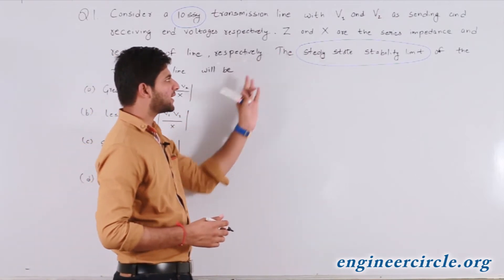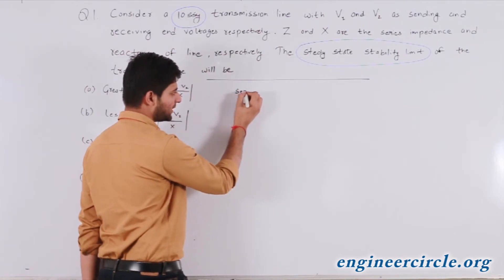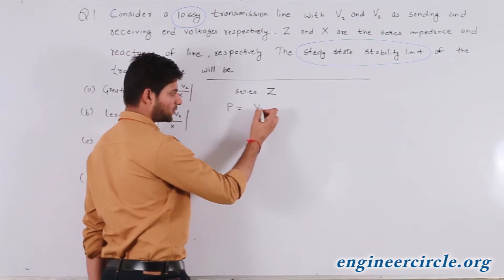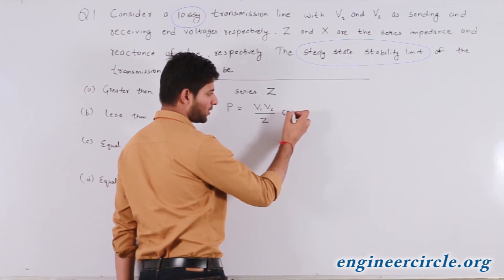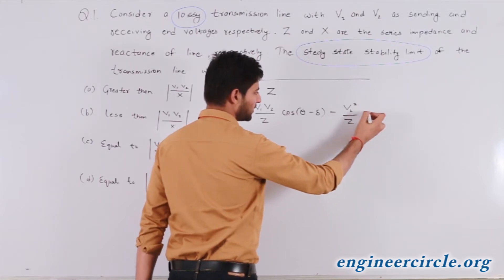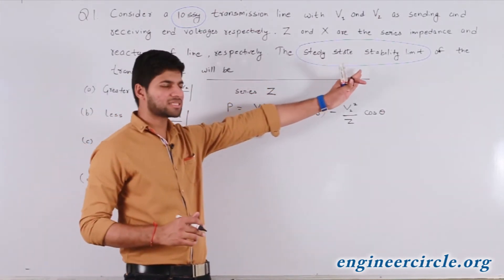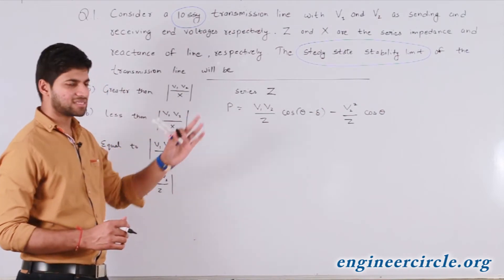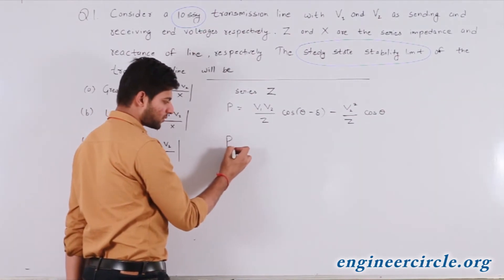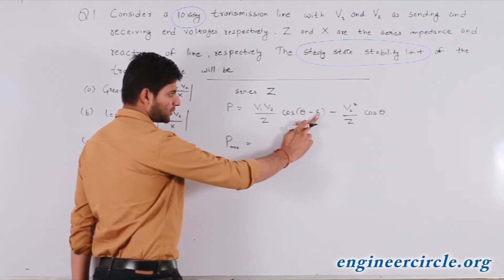As two different types of impedances and reactance are given, we will consider each case separately. When we are considering only series impedance Z, the value of power flow will be equal to V1V2/Z · cos(θ − δ) − V2²/Z · cos θ. For calculating the steady state stability limit, which is the maximum power flow possible in a transmission line, maximum power flow P_max will occur when θ becomes equal to δ.